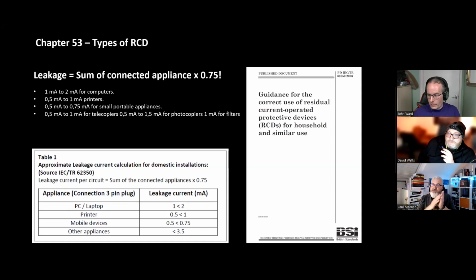And you have to make sure that your leakage meets within the 30% rule. Henceforth, an RCBO helps with that, because if you've got lots of circuits and lots of leakage, it will trip out one RCD. You have lots of RCBOs, you comply. And yeah, so that's basically that standard. It's a lot of money for basically that. A couple of things in the comments there.